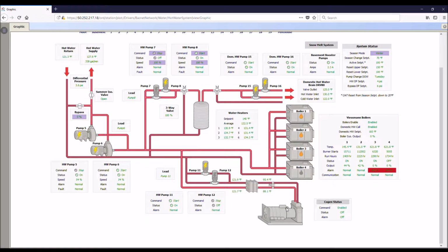We always have flow 100% through the heat exchanger here. So it recirculates its really hot water here, and then the actual heating water is on the other side of this heat exchanger. We circulate water here. Whenever the cogen is running, we always need water circulating here to relieve this heat from the cogen, because it generates a lot of heat, in fact up to 200 degrees. So whenever it does get up to risk becoming steam, it shuts itself off. It has a bunch of safeties and everything to make sure that it doesn't damage anything or vaporize all the water in those pipes. What you'll see is if either of these 2 pumps here, 11 or 12, aren't running, the cogen will trip off on high temperature. So one of these needs to be running in order to relieve that temperature.